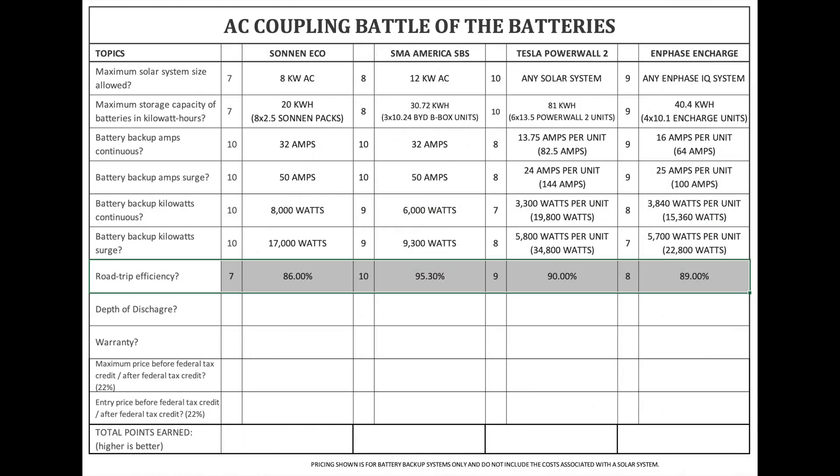Round trip efficiency. This is a very important figure because it has to do with the energy your system loses when batteries are being charged and then discharged. An AC coupled solution will typically have a higher loss of energy than a DC coupled solution because the energy is being converted from AC to DC and then back to AC, whereas a DC coupled solution is DC to DC and then only converts to AC one time. The Sonnen Eco is 86%. SMA America SBS is surprisingly 95.3%. Tesla Powerwall 2 is 90% and the Enphase Encharge is 89%.